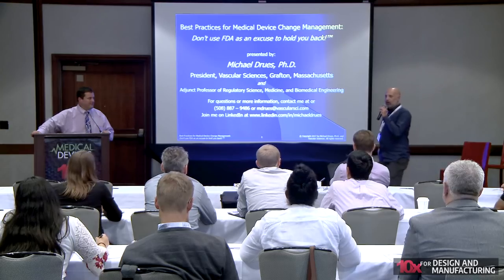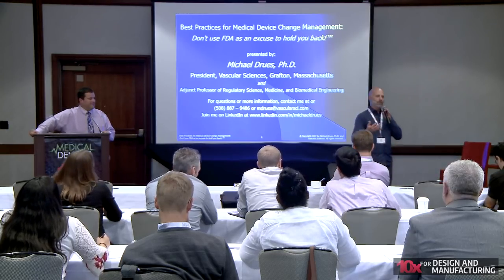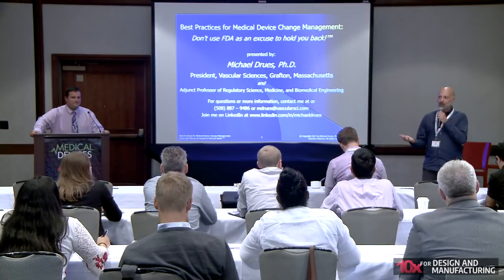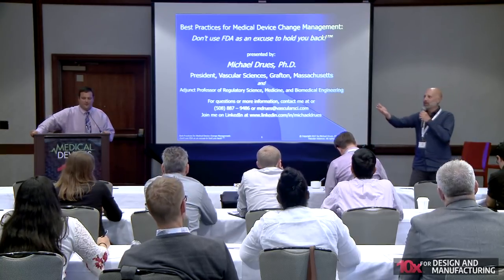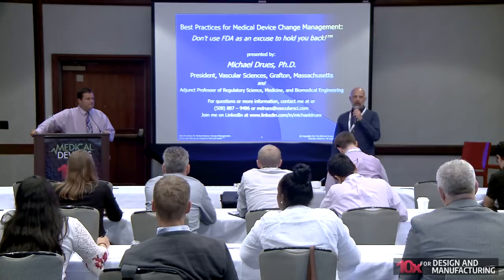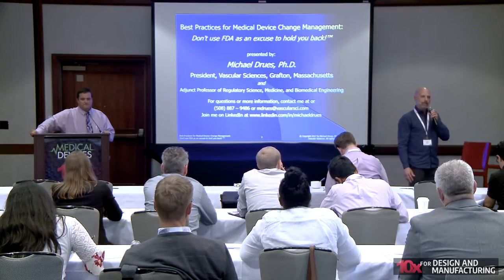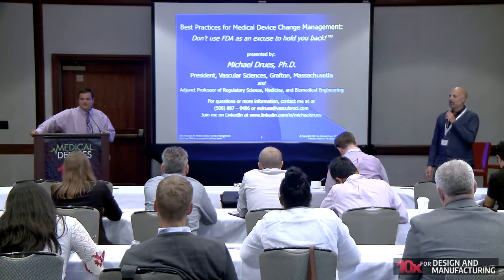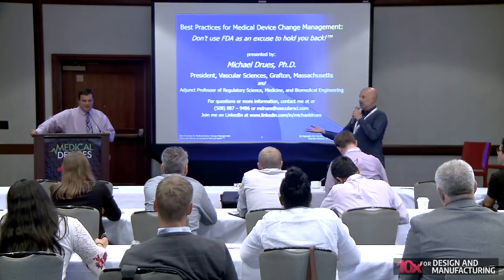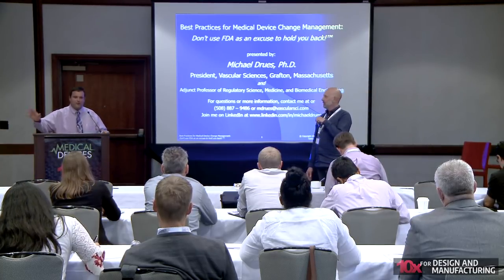All right, so if you're going to notify the FDA, what are some forms that you might communicate a change you're making to the FDA? Special 510K. Are there any other examples you can think of? How about if you're a Class 3 device? PMA supplement, PMA supplement, all right. Okay, so those are ways that we can notify the FDA.